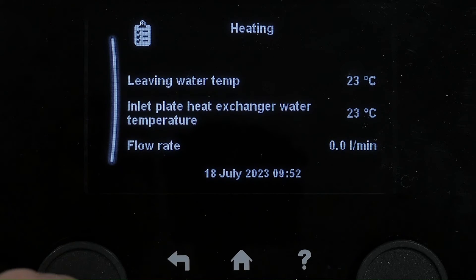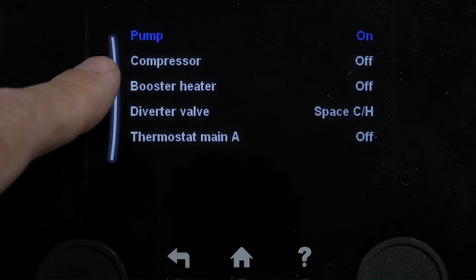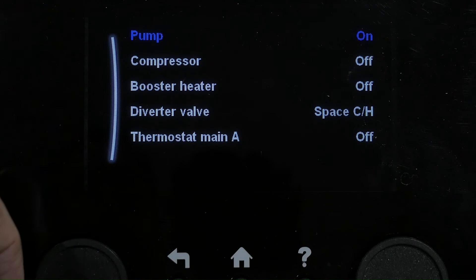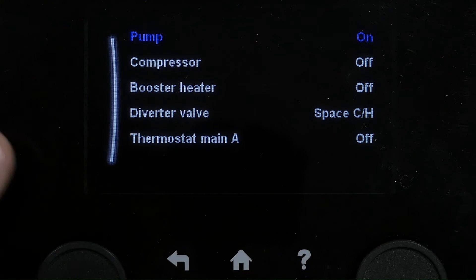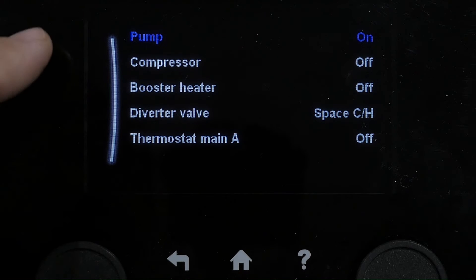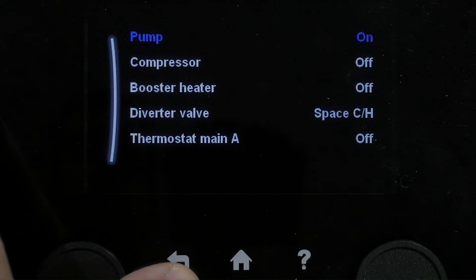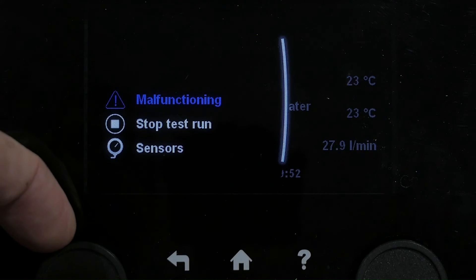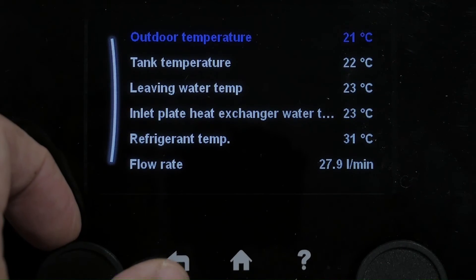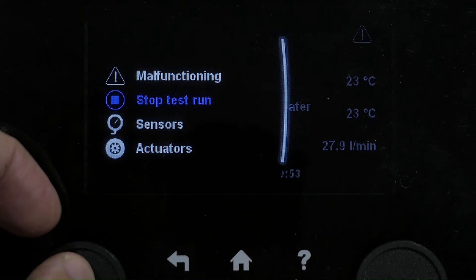In heating mode, the unit's just about to start up. We can check our actuators to see what's happening — the pump has just come on. It's going to run for a little while, and then eventually you'd see the compressor activate. The diverter valve is there. You can see our flow rate is good. We can check our other sensors to see how the unit is functioning. We'll stop this test run here.